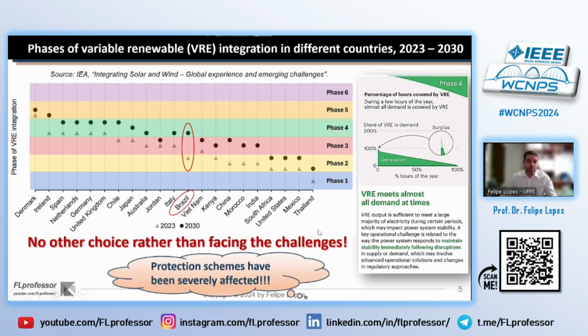And in this context, we know that protection schemes have been severely affected. This is why we are concerned about studying alternative solutions to protect the systems that interconnect these IBRs, because historically, we have heard a lot from utilities that several problems have taken place in real systems, especially regarding the reliability and security of protection functions, because these types of generation change the fault response. And at least what we have heard is that some of the conventional protection is not able to properly protect the systems under certain conditions of operation of these generations.